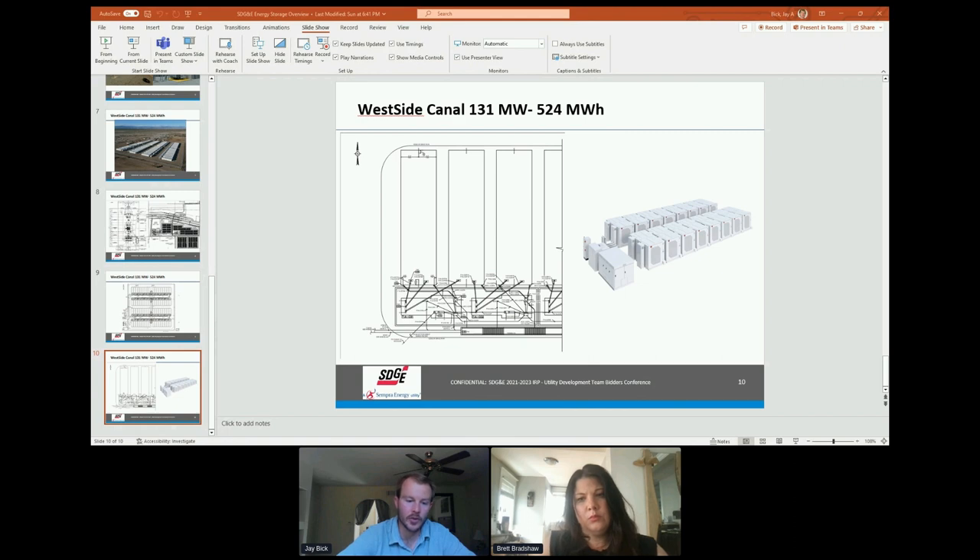With later-generation systems, as you'd expect, inverter manufacturers are getting better, battery providers are getting better, and integration software is getting better — that's really the key. Maintenance is super crucial. These are all liquid-cooled — the earlier products were all air-cooled. The advantage of liquid cooling is that with 26 cells in a module, it's really hard to get cool air to the center of that module, whereas liquid cooling ensures ubiquitous temperature control for all cells. On air-cooled units you'd see more degradation on cells in the middle versus those closer to the HVAC outputs. HVAC maintenance is a huge priority. As soon as you're seeing HVAC alarms or temperature deviations, you need a truck roll to recover that asset. Many warranty parameters for batteries are very restrictive — you will lose your warranty if batteries sit in the desert without temperature control.